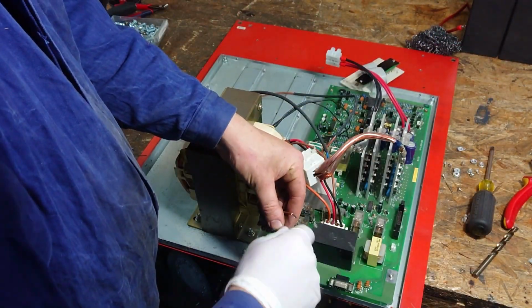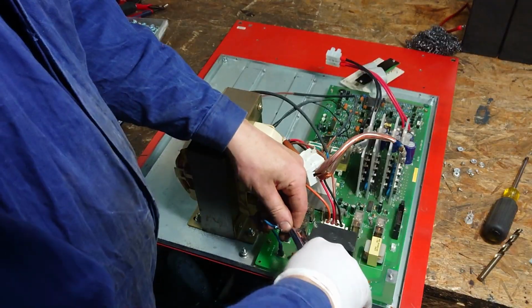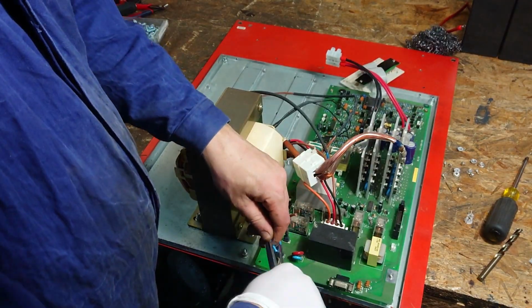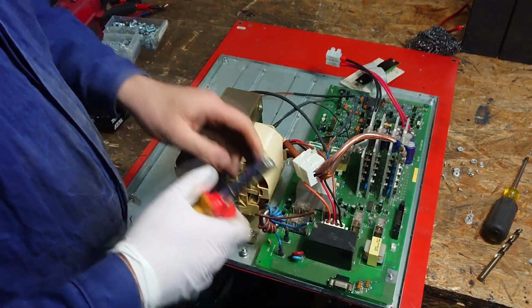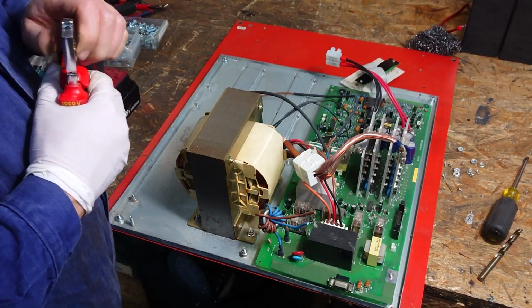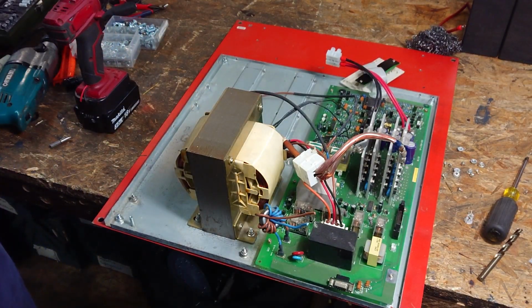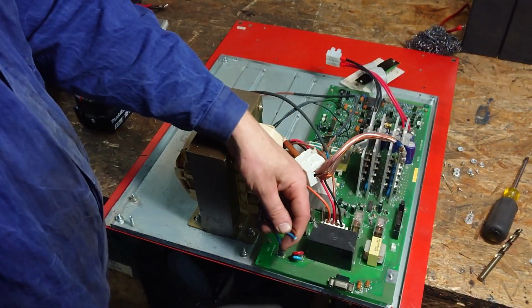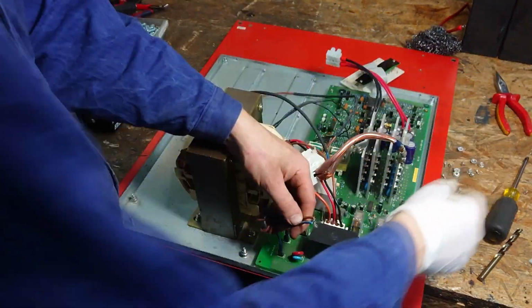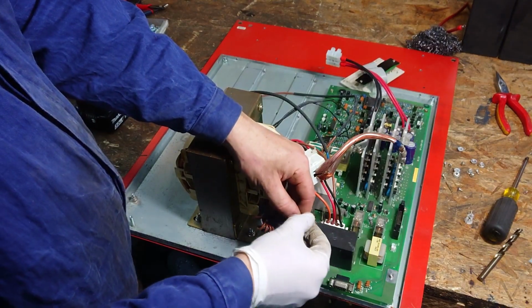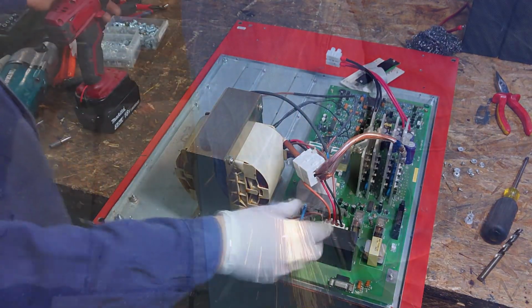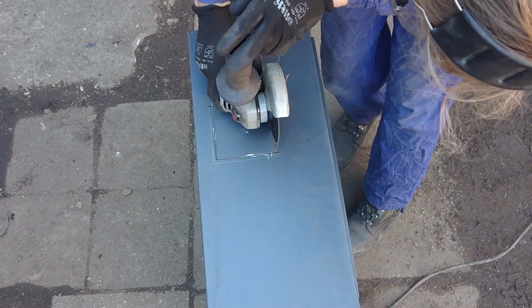Just a word of caution: uninterruptible power supplies are designed to run at high power only for a short duration, namely until the server is shut down safely in case of a blackout or until the batteries are drained. So in other words, the power rating on the front panel is only a short-term power rating. It will overheat if you run it at 2.2 kVA continuously, but I think it will be able to run at a couple hundred watts for long durations, and we will just have to see about that. In case it overheats, it even has a heat sensor inserted into the transformer, by the way.